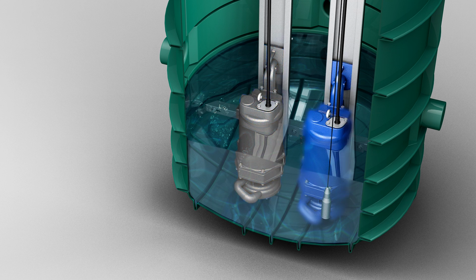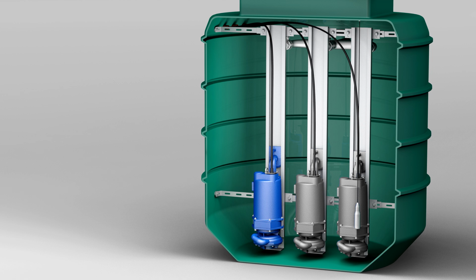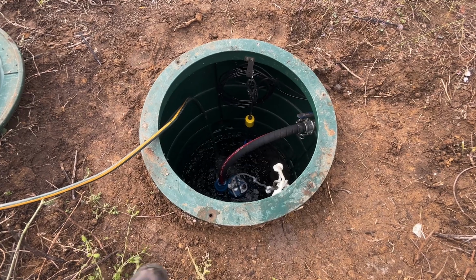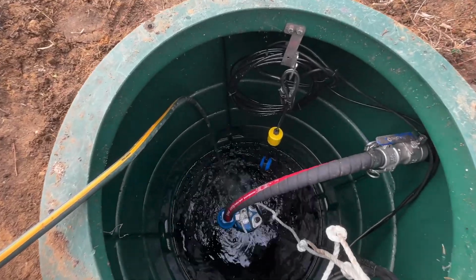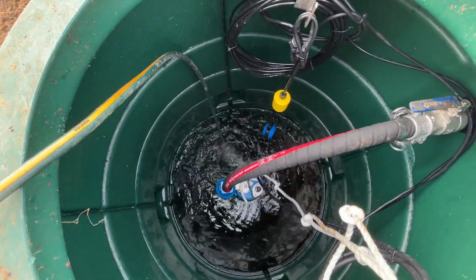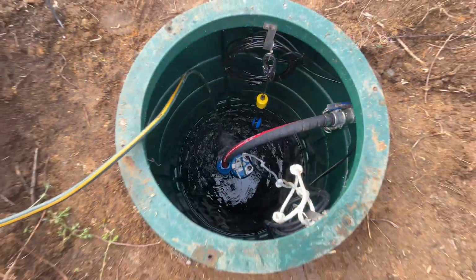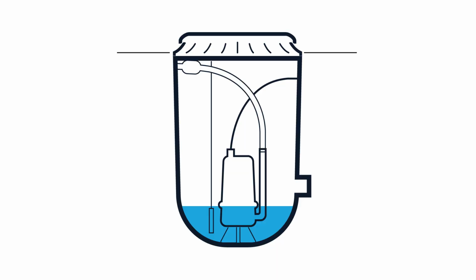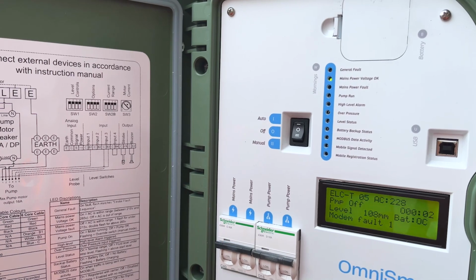Each start cycle will switch to the other pump in any multi-pump system. You want to check that the cycle has rotated through each one of the pumps. There's a test procedure written in the commissioning document which states as follows: introduce test water to the chamber until the pump activates. Now confirm that the pump start level is below the inlet to avoid any surcharge of your gravity incoming, which can ultimately cause blockages.